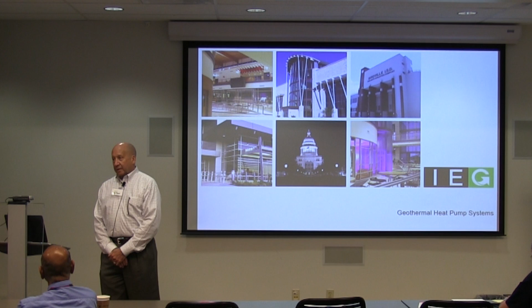But that's with relatively high ground temperatures, we're around 70, 72 degrees for heat rejection. We pulled the last several projects and looked, and the price varied by $5 a foot. It just depends on when you hit who. All the projects are within budget, but one may be $18 a foot and the next may be 23 - there's no rhyme or reason.